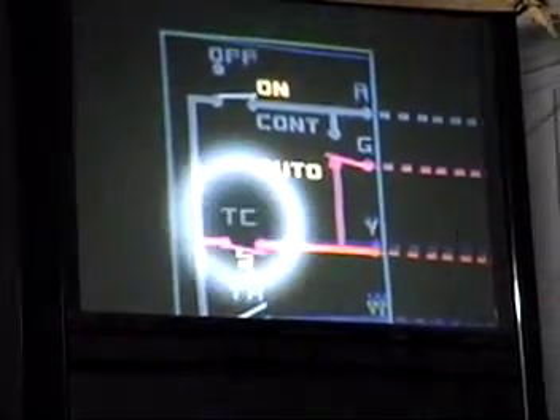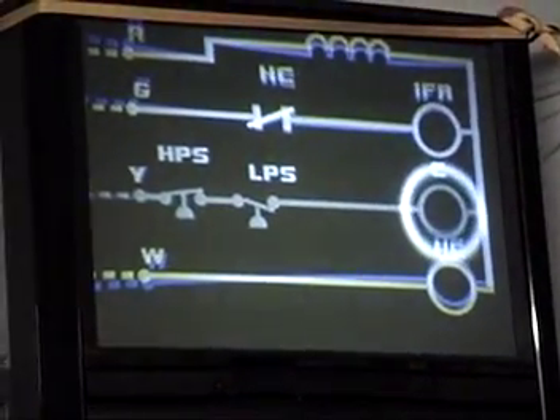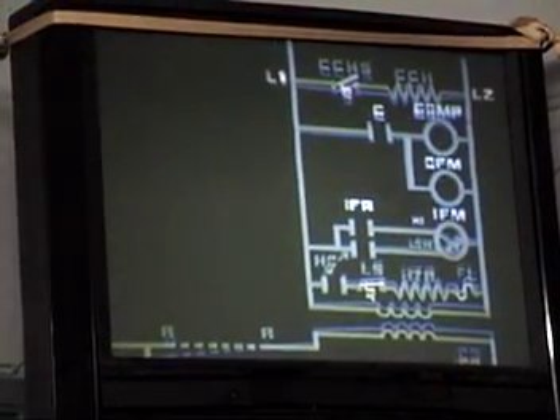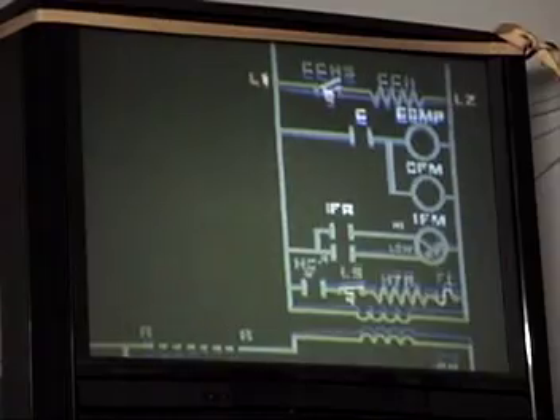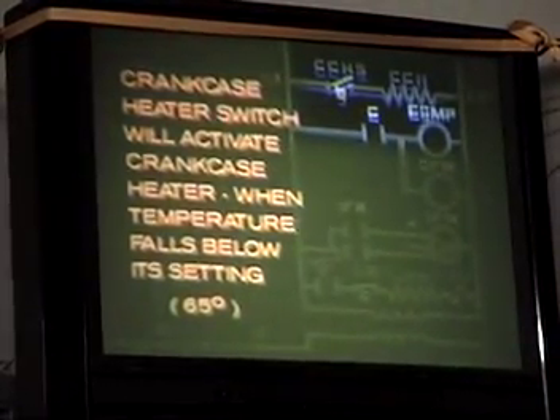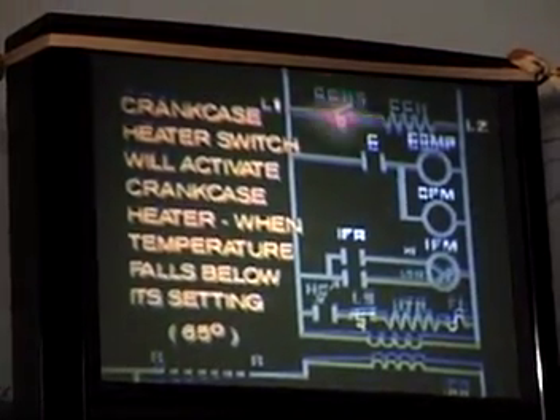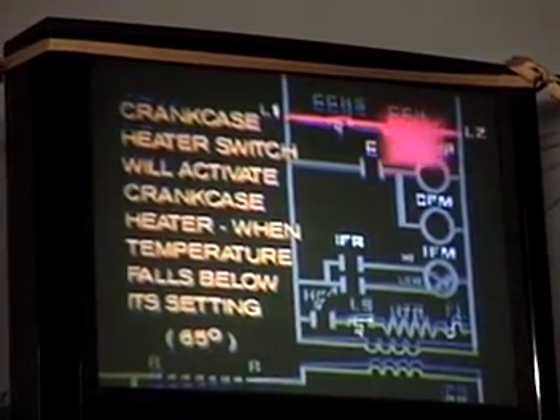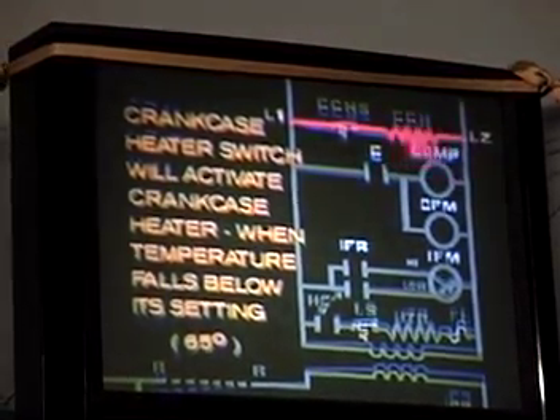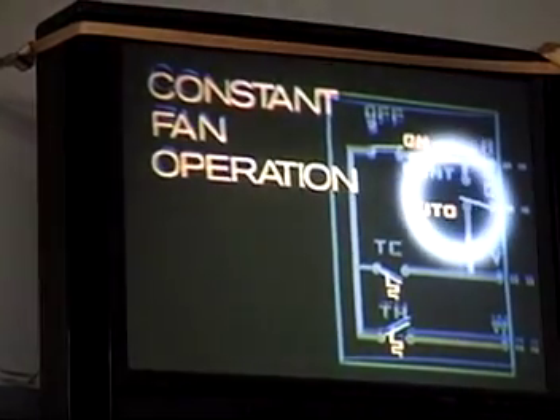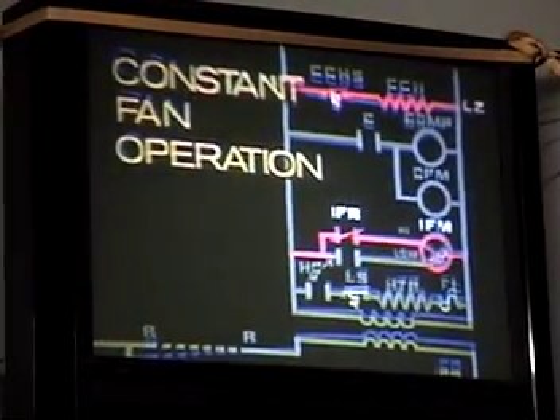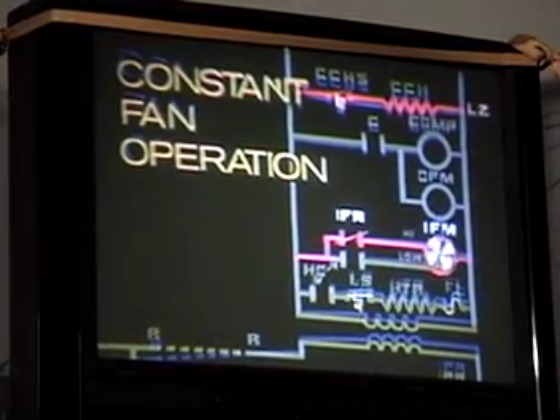Indoor and outdoor fans move air to lower the occupied space temperature. When the desired temperature is reached, the cooling thermostat opens and de-energizes the contactor and the indoor fan relay. This opens contacts in the power circuit, and the compressor, outdoor fan motor, and indoor fan motors stop. The transformer remains energized, and if the temperature of the crankcase heater switch drops below its setting, let's say 65 degrees, it closes and activates the heater to warm the compressor and prevent refrigerant floodback. If constant air circulation is desired, the fan switch can be set at continuous. This will energize the indoor fan relay, and the indoor fan will run to maintain air circulation through the occupied space.